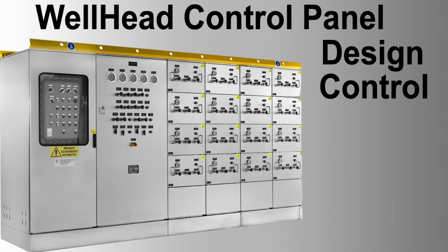4. Instrumentation. Function. Sensors and transmitters for pressure, temperature, and flow measurements. Construction. Intrinsically safe or explosion-proof designs. Materials. High-grade alloys, Teflon coatings for chemical resistance. 5. Piping and tubing. Function. Connects various components within the WHCP. Construction. High-pressure, corrosion-resistant piping and tubing. Materials. Duplex stainless steel, Inconel for sour service.